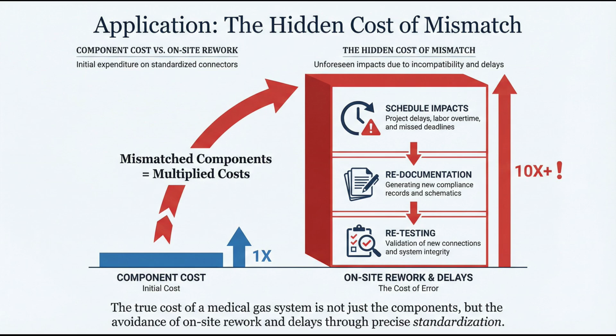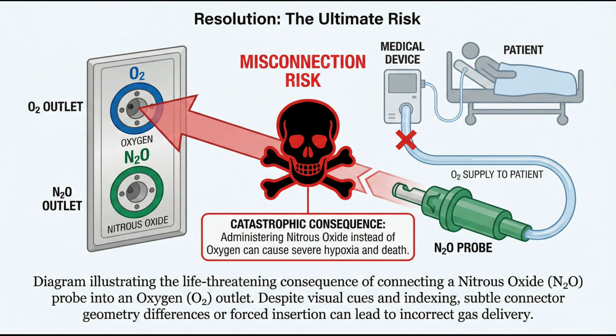When a mismatch is discovered, the cost isn't the component, it's the rework. Retesting, recertifying, and delaying the room's opening can consume the entire contingency budget. But the ultimate cost is far greater than money. The ultimate consequence is lethal, supplying the wrong gas to a patient. When systems are mixed, engineered safety guards are compromised, leaving only human vigilance to prevent a fatal error.